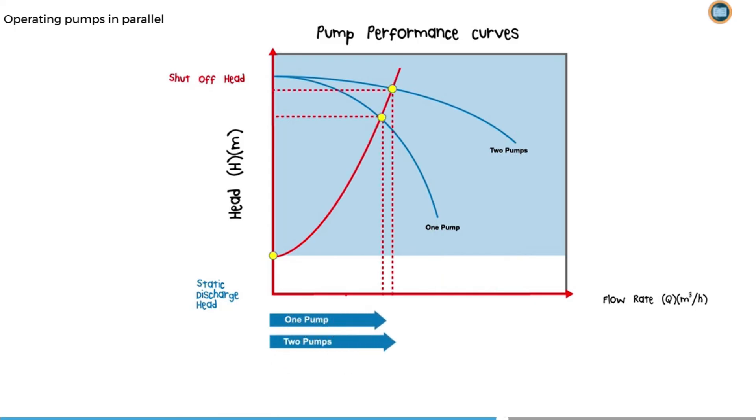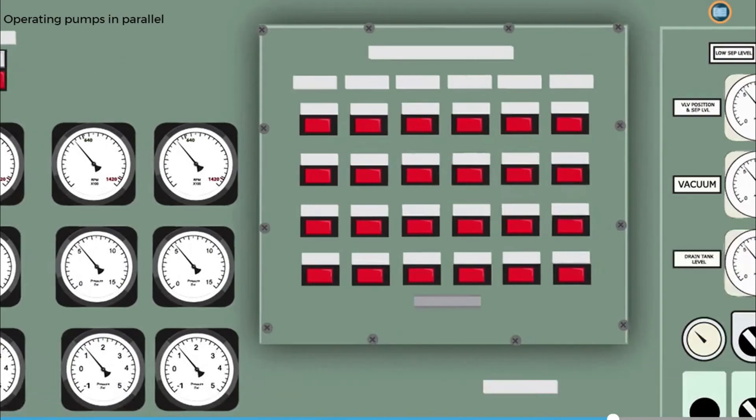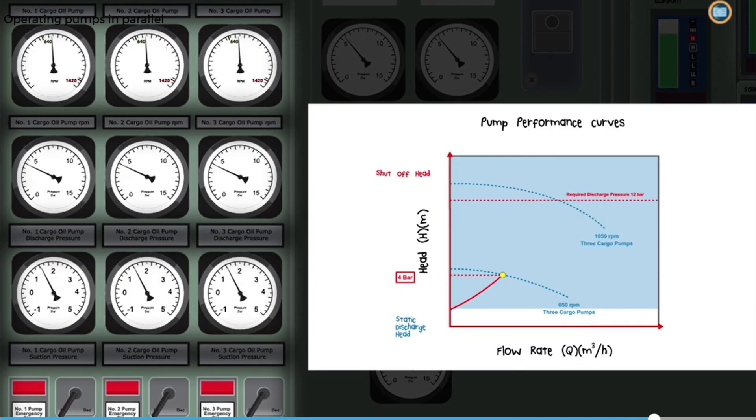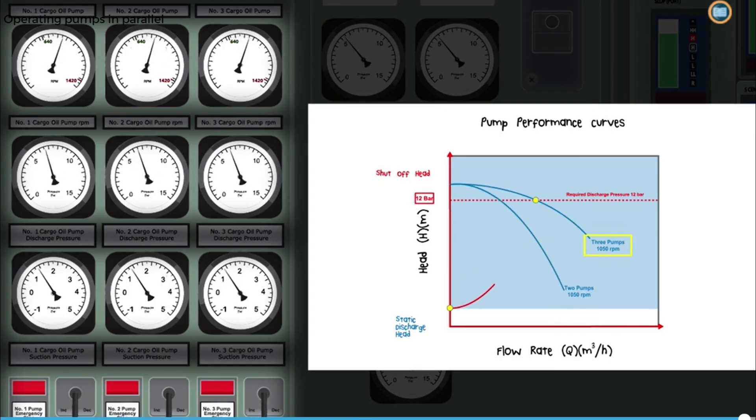When there are high shore resistance conditions, operating two pumps only increases the overall flow rate slightly more than if one cargo pump is running, but the discharge pressure increases significantly. When operating three pumps, the increase in flow is hardly noticeable, but again, the discharge pressure increases significantly. Under these high shore resistance conditions, paralleling three cargo pumps requires careful control to match the pump discharge pressures. When operating in parallel, the rotational speed of each pump should be increased in steps of 50 or 100 RPM. Between each step, the discharge pressures should be seen to settle before increasing any further. When possible, it is always more efficient to operate two pumps at or near full rotational speed rather than using three pumps at a reduced RPM.